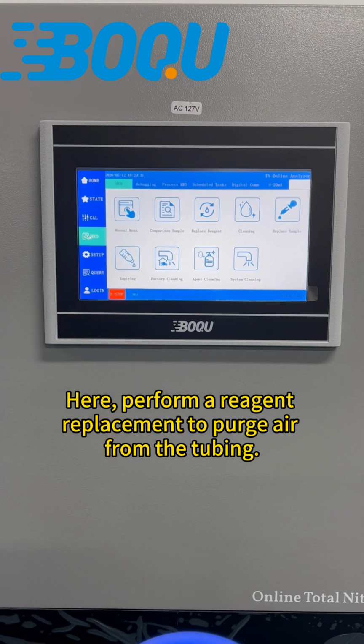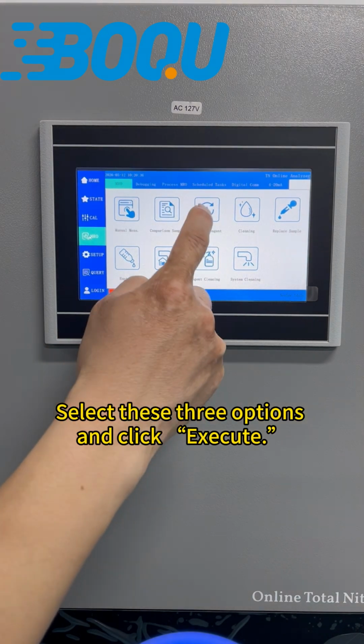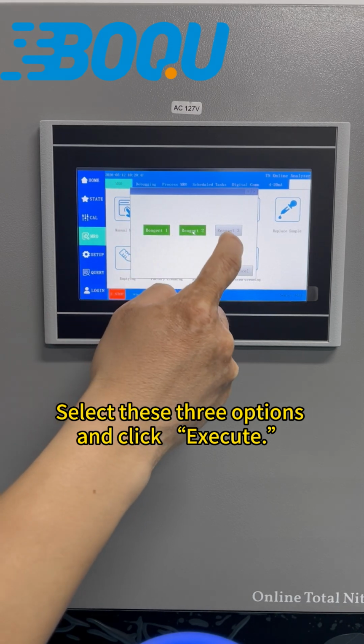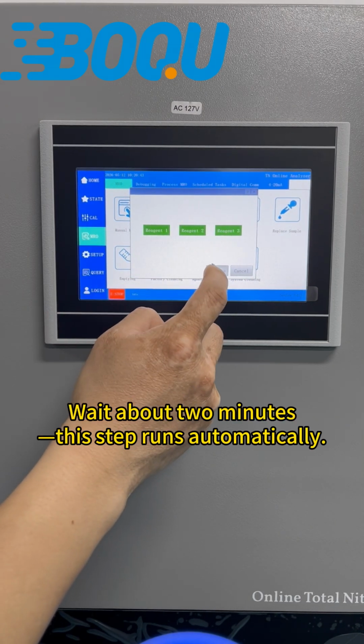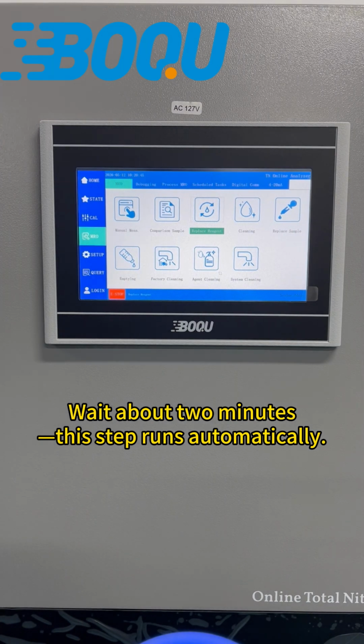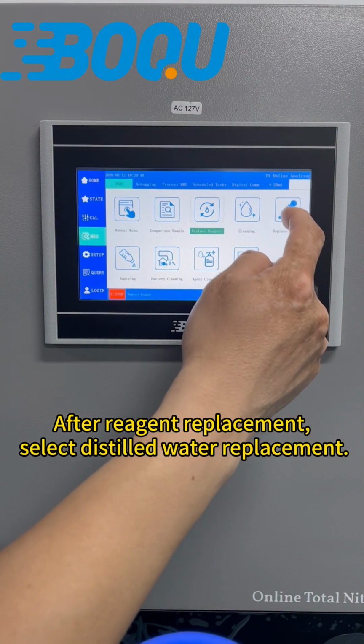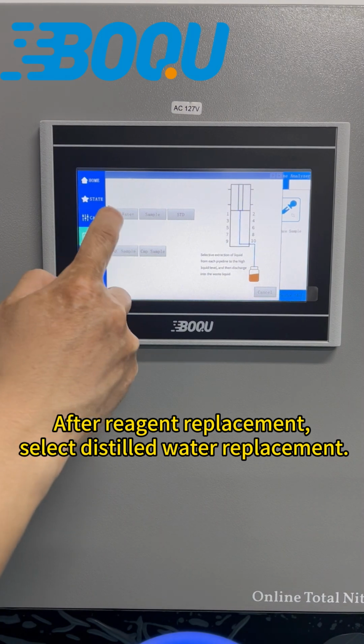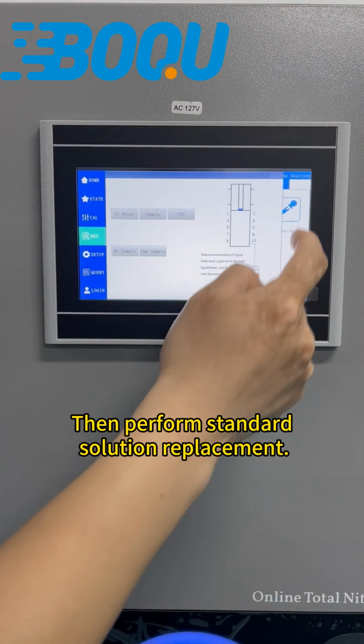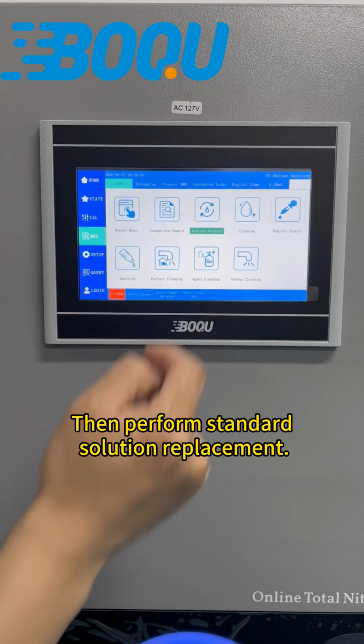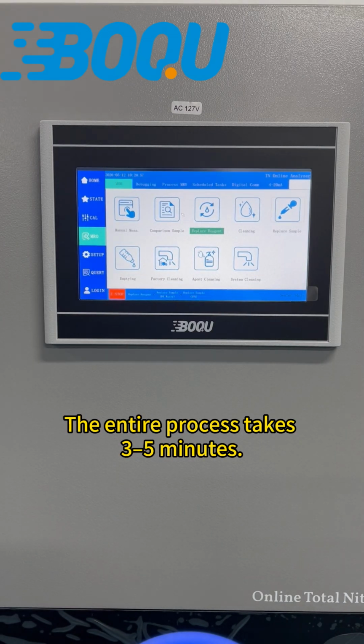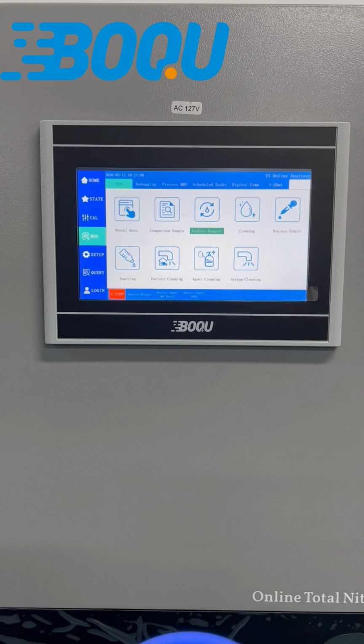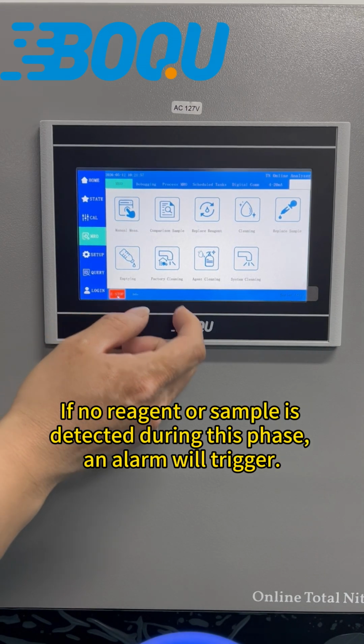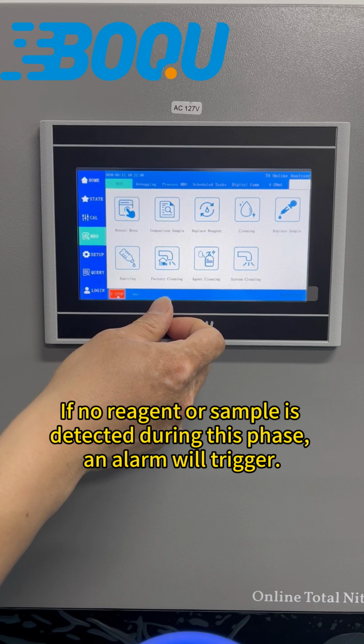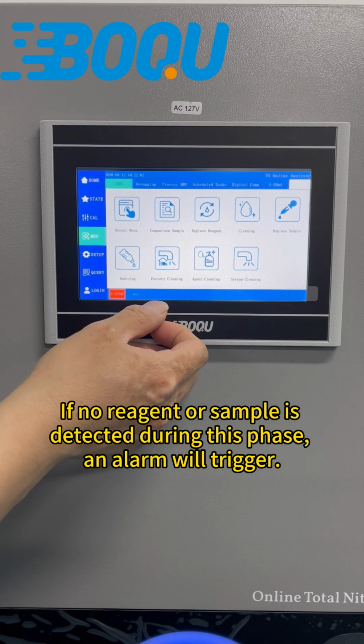Here, perform a reagent replacement to purge air from the tubing. Select these 3 options and click Execute. Wait about 2 minutes. This step runs automatically. After reagent replacement, select distilled water replacement. Then perform standard solution replacement. The entire process takes 3 to 5 minutes. If no reagent or sample is detected during this phase, an alarm will trigger.